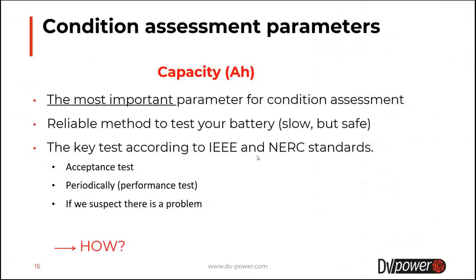As I previously said, the battery capacity test is the most important parameter for condition assessment, and it is a reliable method for testing your battery. It is a slow but safe test. As we saw, the C5 test is a 5-hour long test, but it is even longer when you count in the preparation for the test, mounting equipment and connecting everything. After performing the discharge test, the battery needs to be recharged. This is a key test according to all standards.